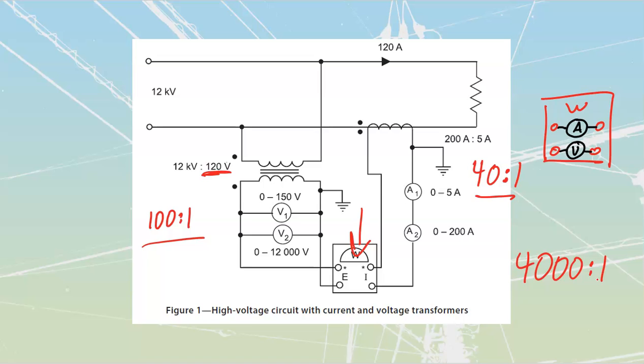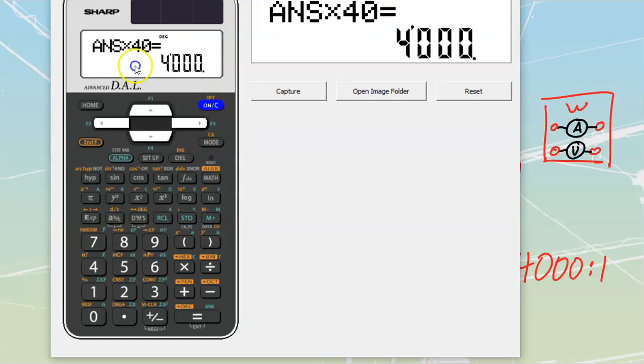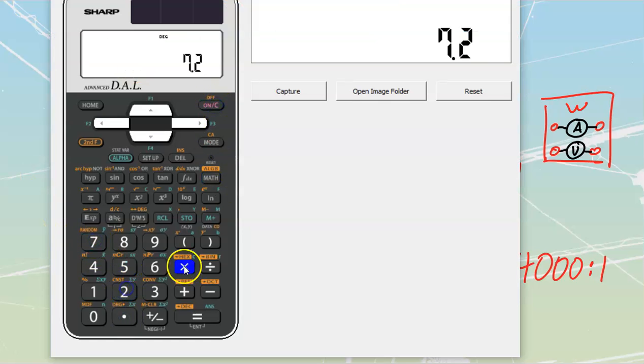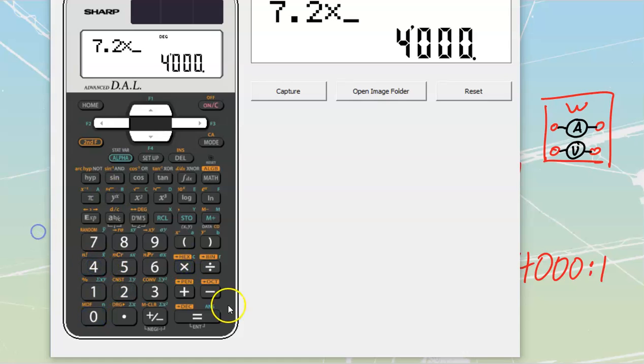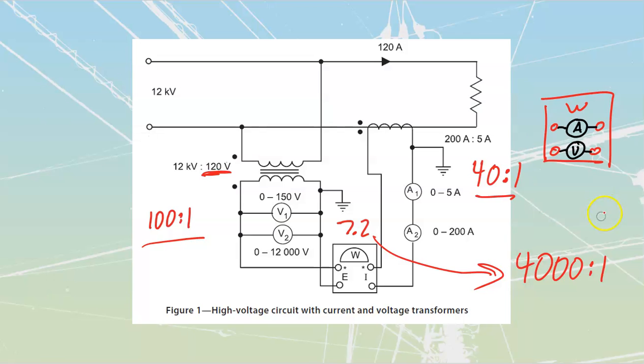Which means that whatever I'm seeing on that watt meter, if I'm seeing 7.2 watts being read by that watt meter, I'm going to take that 7.2 value and multiply it by 4,000. Let's just try that. 7.2 times 4,000 equals 28.8 kilowatts that my load must be drawing.